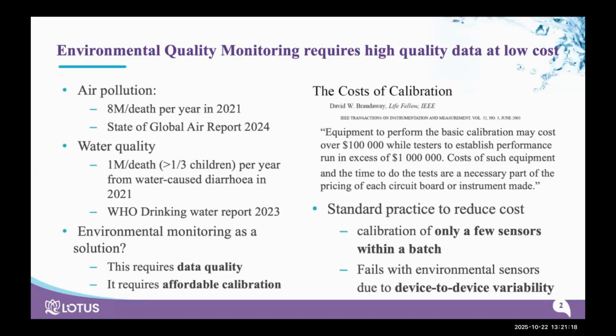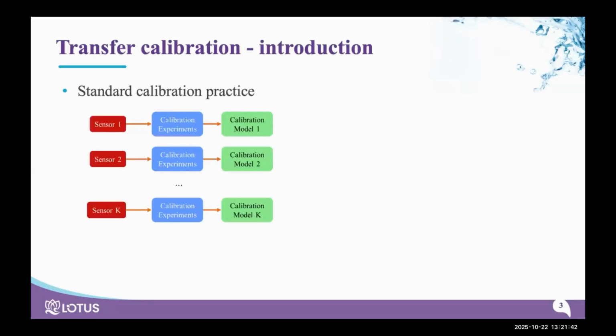What happens in practice is that a lot of sensors are sold with no calibration, and the calibration is done on a couple of sensors of the batch. This works very well for temperature sensors and strain gauges. This works perfectly. It doesn't work at all for environmental sensors. No way, no how, with the present status of the technology. So you're back to calibrating each device one by one, which is very expensive and brings up the cost. It raises the cost of the environmental sensor by a factor of 10. I'm talking from experience, okay?